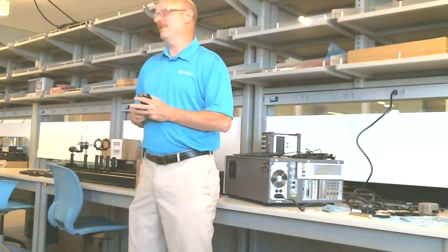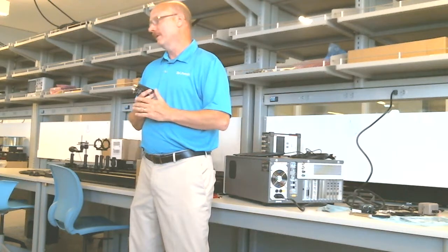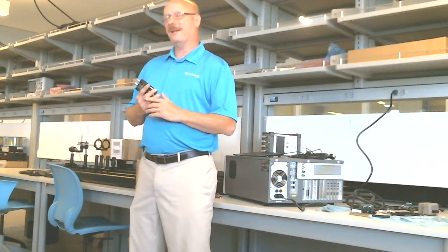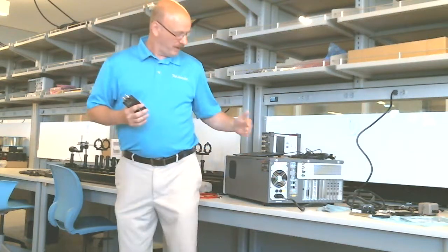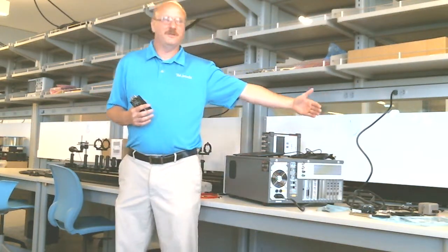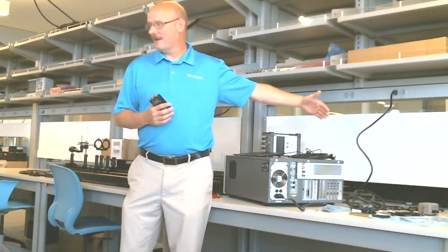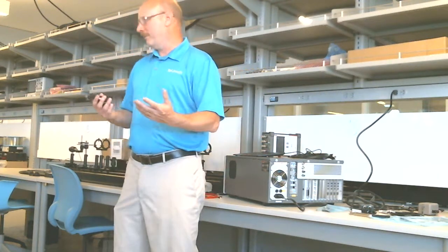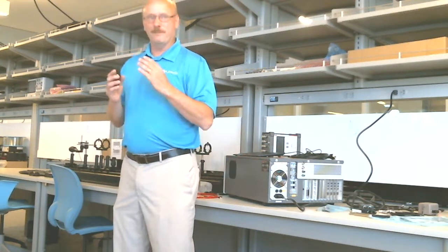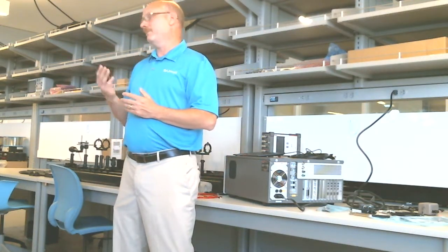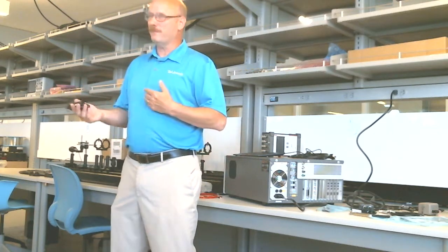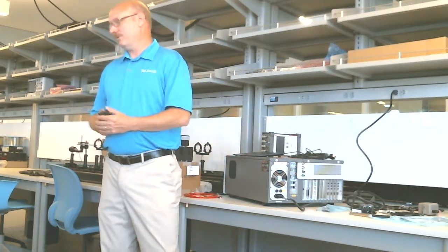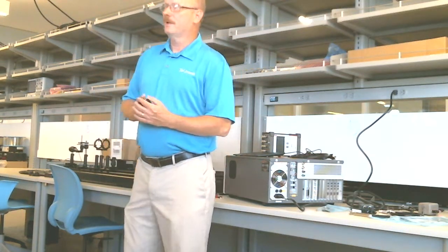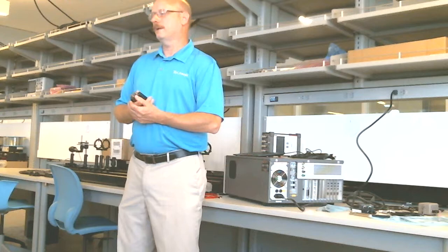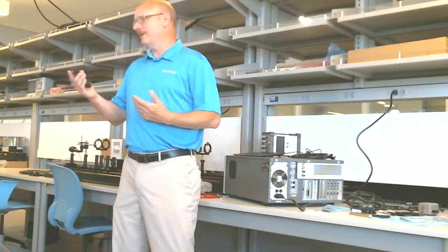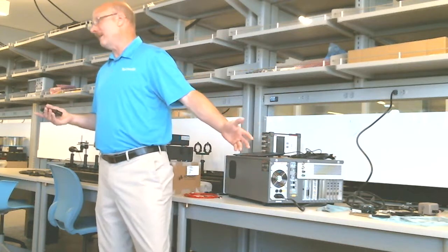We have new SMUs that just came out that are field installable that you can purchase. They're calibrated to a much tighter standard, so they will work across the whole backplane. They're designed to work in any slot, and basically they're cherry-picked SMUs that they were able to calibrate really tightly. So they sell those at a premium. There's a price to pay for them. They're a little more expensive, but you can purchase those. You can plug them in yourself and use them. That's also nice if you want to add an SMU. You'll never need to add an SMU. You have 4 SMUs. Actually, you have 5. I'll explain that.